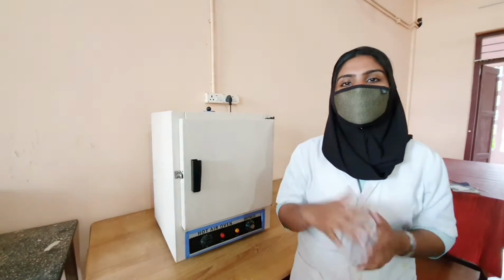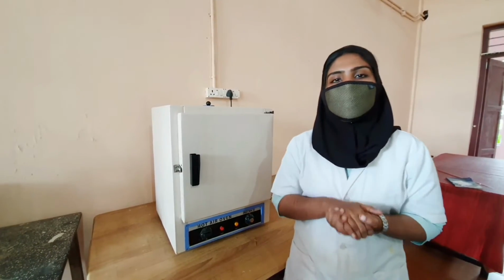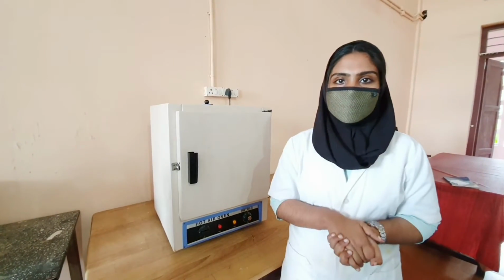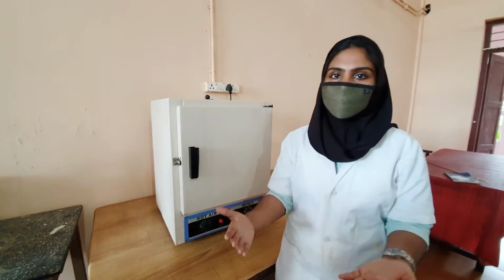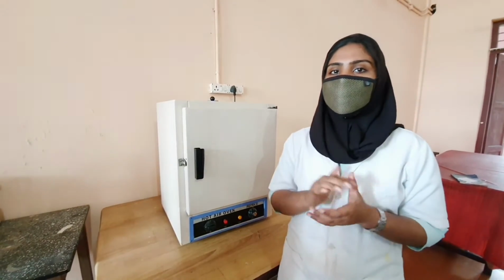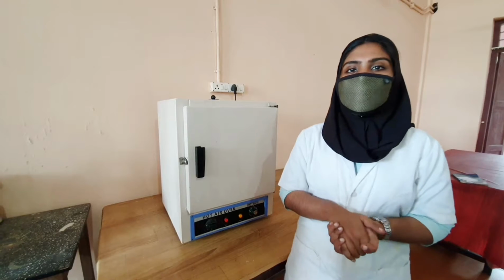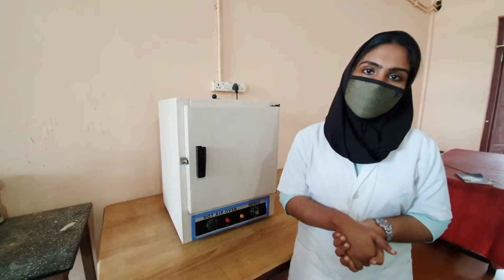The working principle of the hot air oven is sterilization by dry heat, and it is performed by conduction. The heat is absorbed by the surface of the objects, then moves towards the core of the object, coating by coating. The whole object will ultimately attain the temperature needed for the sterilization to take place.